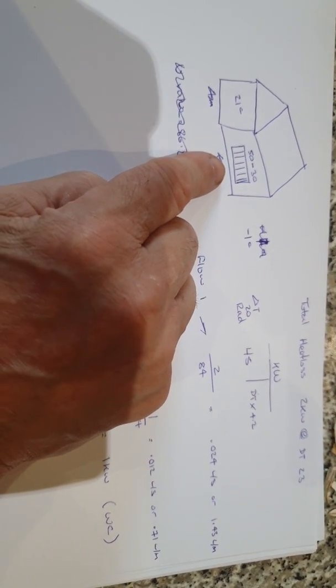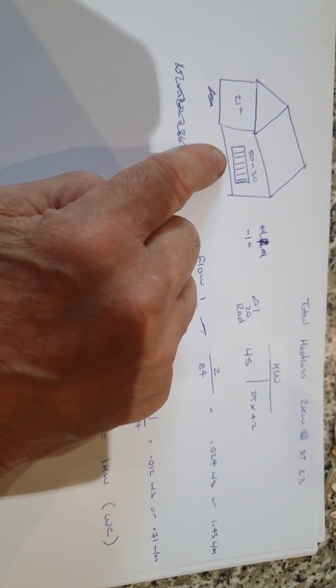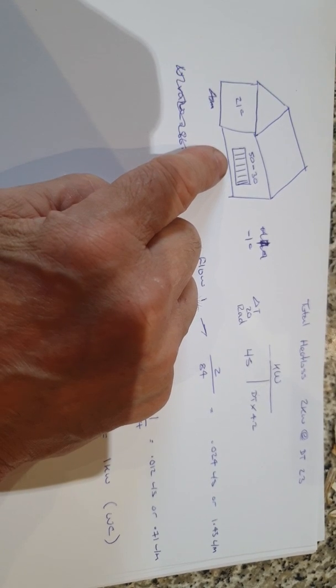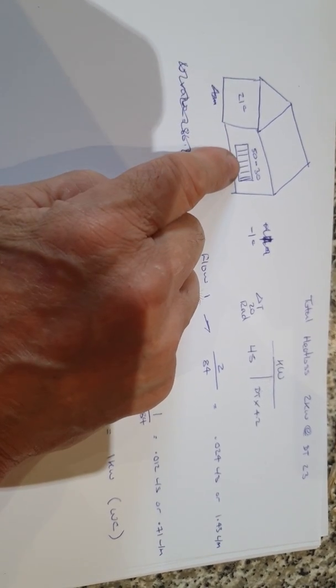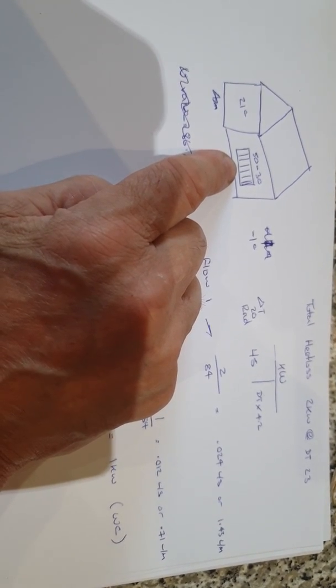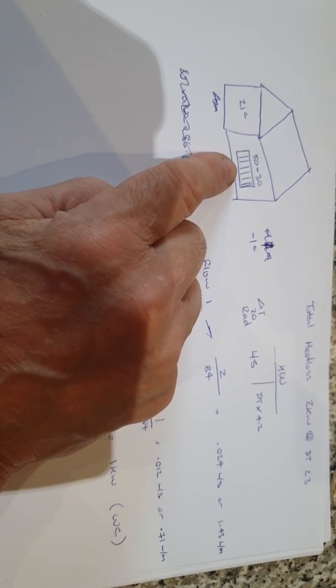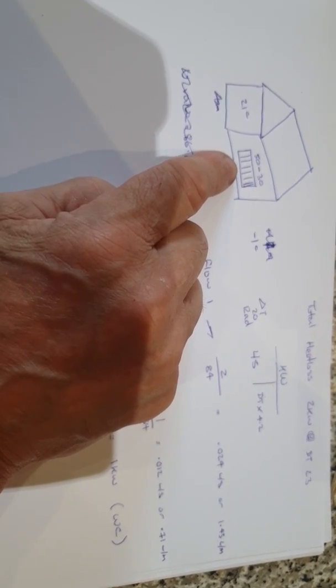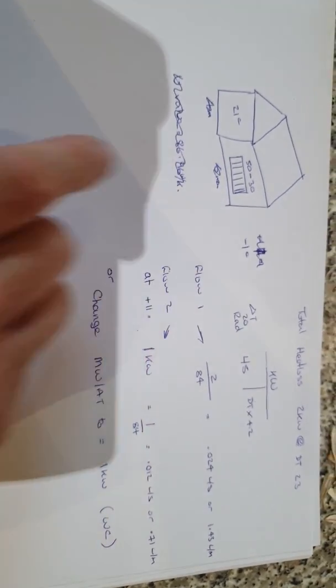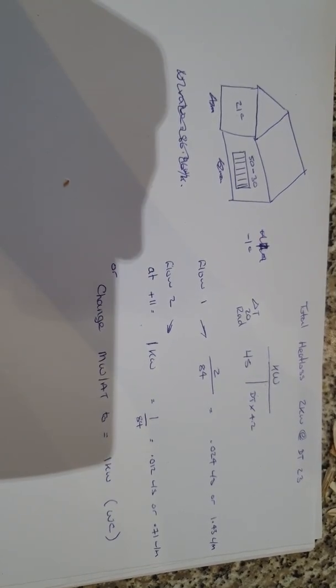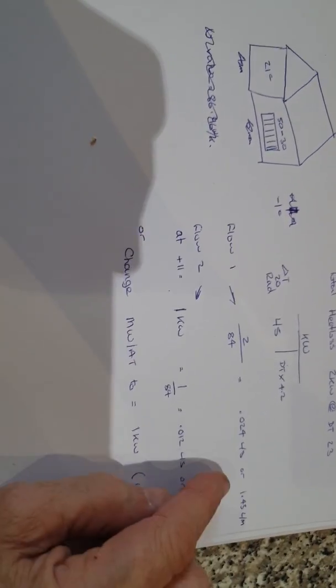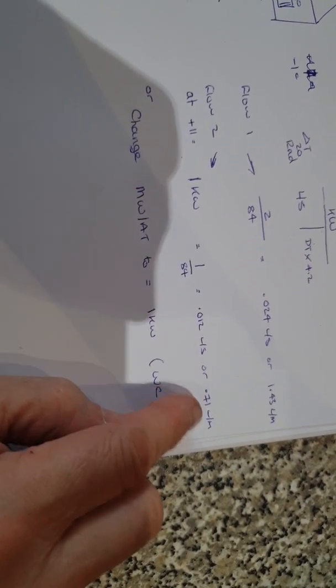We could say, okay, well we're going to get a heat loss if we maintain 21°C of one kilowatt, and the delta T should now be 10. If we've got a fixed rate pump, the flow rate's not changing but the energy out is, and we're only going to get one kilowatt out to maintain the 21.